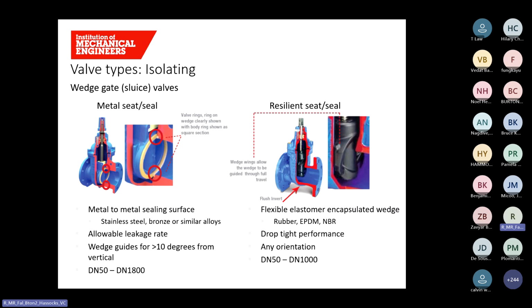Wedge gate valves in general are suitable for buried applications. They can be installed in any orientation. However, for metal seated, anything installed 10 degrees or more from the vertical typically requires wedge guides. These valves are available in a large size range, but typically anything above DN 1000 is likely to be the metal seated variant.